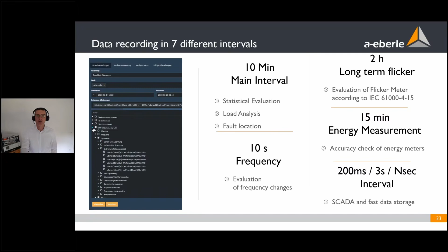The frequency, in case of EN 50160, as well as other regulation standards, can be recorded over the 10-second interval, 2-hour interval, 15-minute or n-minute interval for energy measurement. Accuracy check of energy meters is an application, therefore, as well as the regulation in case of industry. And we have faster intervals, 200 millisecond, 3-second, n-second interval for SCADA, as well as for the fast data storage. Up to 3,000 measures are possible here in each interval.